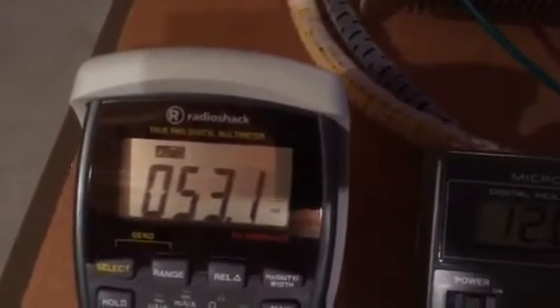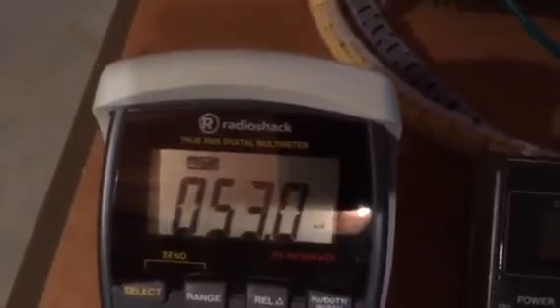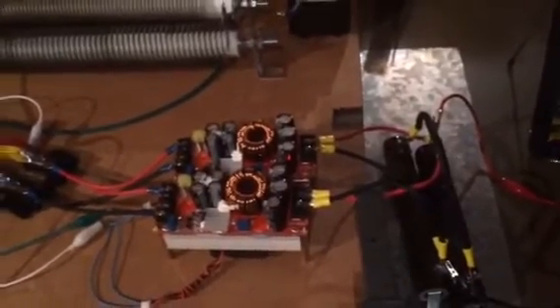Now you can see my output's 50 volts, my input 12 volts. I'm using this multimeter with a Fluke current gauge right here, snap-on current gauge. I'm going to put this on the first power supply. You can see the output there. And let's go over and look at the current. Look at that, no current. Interesting. And yet my loads are really heating up here, so we got current somewhere. Now let's snap it on the second output. And you can see we got 5.3 amps. So you can clearly see in this arrangement, even with the output voltages adjusted independently and even with the identical terminations, I still have a significant load sharing problem.